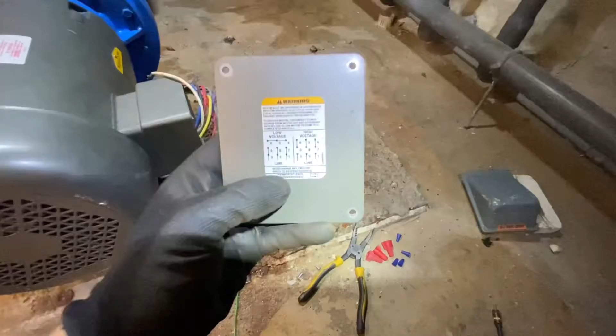Okay, so wiring, this would be considered a dual voltage motor, or maybe a multi-voltage motor. So notice the wire diagram says low voltage, and you've got a diagram, and high voltage, right? So usually high voltage is 460, 480, low voltage is 208, 230. But you can't always assume that.